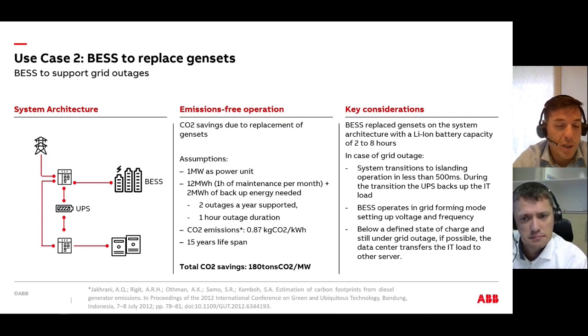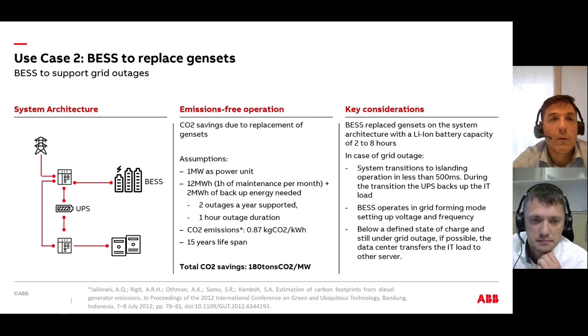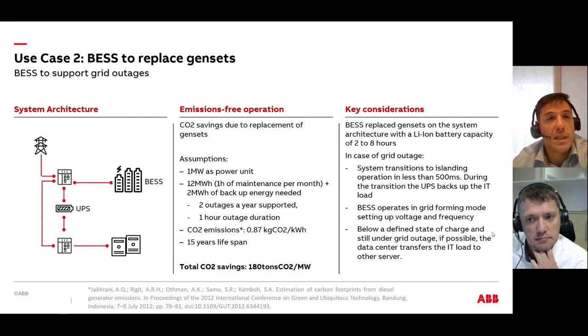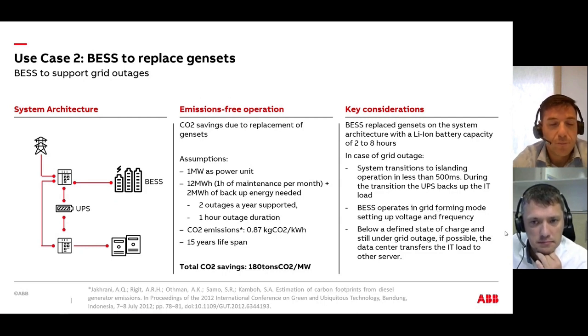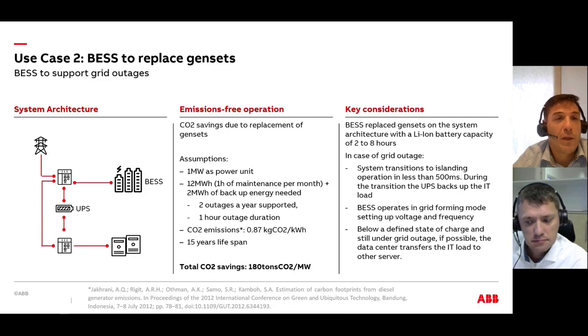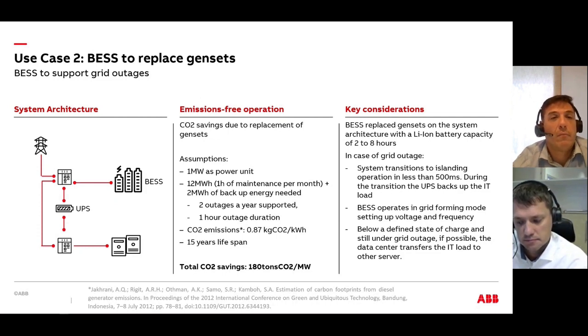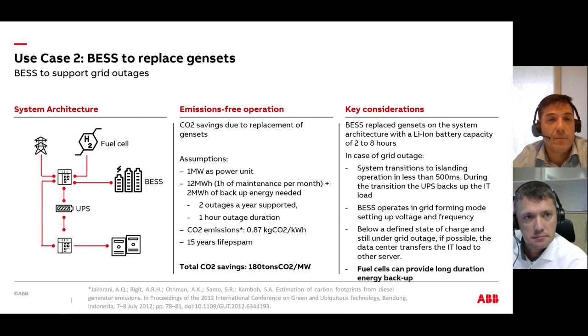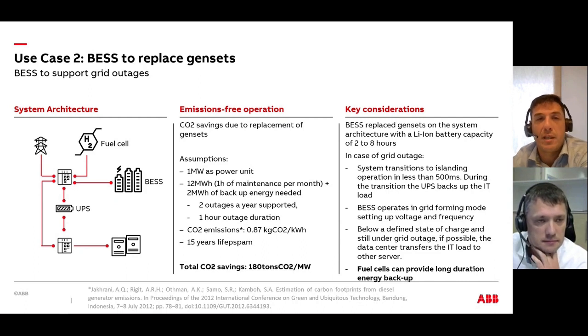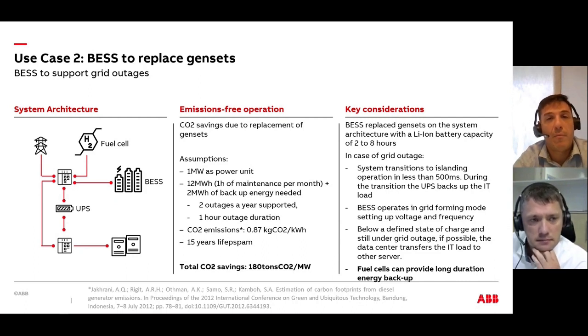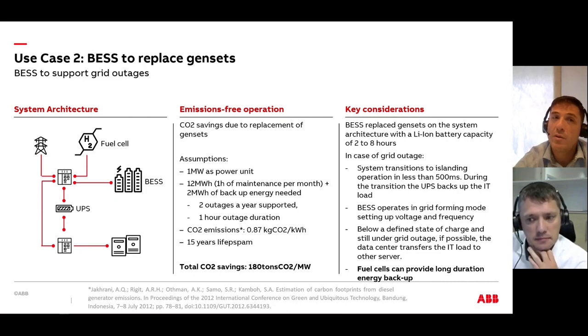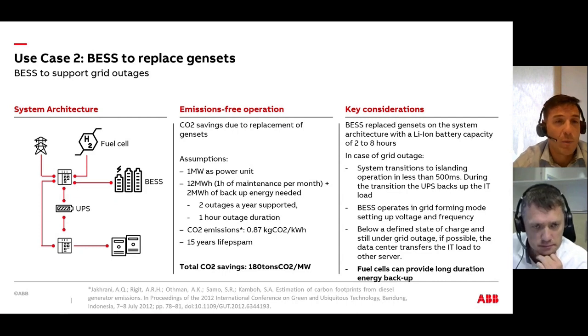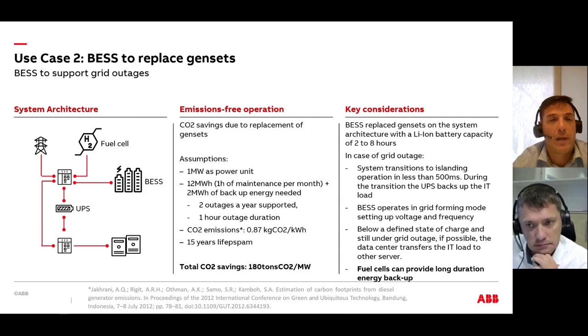But if we consider what we can do, we can add a fuel cell into the system or any other source. The fuel cell is going to be connected as well in parallel with the grid and with the BESS. So this fuel cell can provide the long duration energy backup that is needed. If the fuel cell is there, the main thing is that the BESS can then be reduced in energy capacity. We don't need those 8 hours. The 1-2 hours that we had before in use case number one is enough because the fuel cell will run in parallel with the BESS.